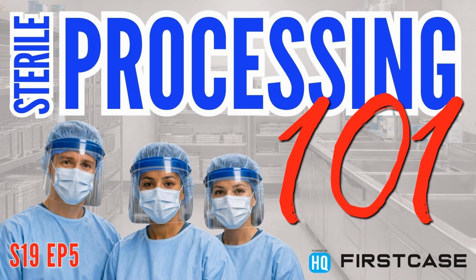And when I say we don't know for sure, it doesn't mean that we can't be confident, because we can. In a proper rigid container system that's been properly maintained and that instrument has been kept in the right environment, it definitely is sterile. But there are things that could happen to that tray that might hurt our sterility assurance. So if you're using a rigid container system, there's a giant ding in the side of the lid such that you can actually see a little bit of a gap down into the rigid container, then you should not feel good just because there's a pass indicator right next to the instrument, right? So we need to be checking our trays to make sure that the packaging is appropriate. There's not holes in our wrapper, or the seal of the rigid container, actually, the lid fits on the base of the container and things like that, in addition to checking that there's an indicator on the inside.